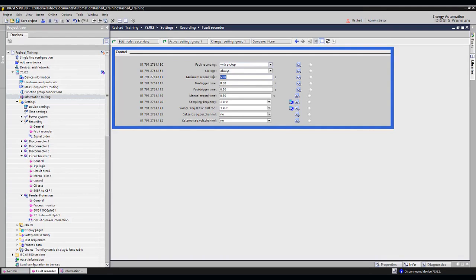I should set it longer than the longest delay time for any function I have. But that's not all. Additionally, there's the possibility that the breaker hasn't tripped, so I need the breaker's time. Plus, the time after the breaker has tripped, to account for all the breakers that have tripped. If I just do it and the voltage completely stabilizes, all of this needs to be taken into consideration. With the work of the lockout relay itself, with the output contact delay time, and with the aging of the circuit breaker, you set a margin for yourself and so on.